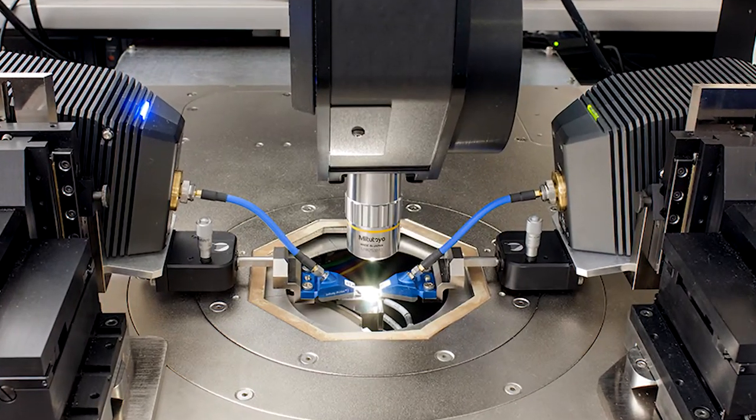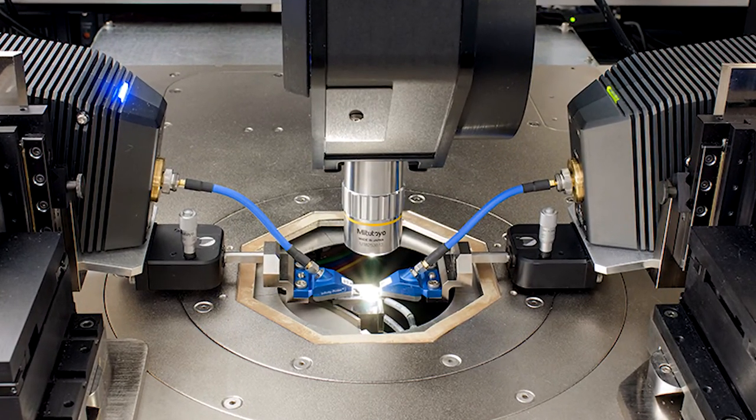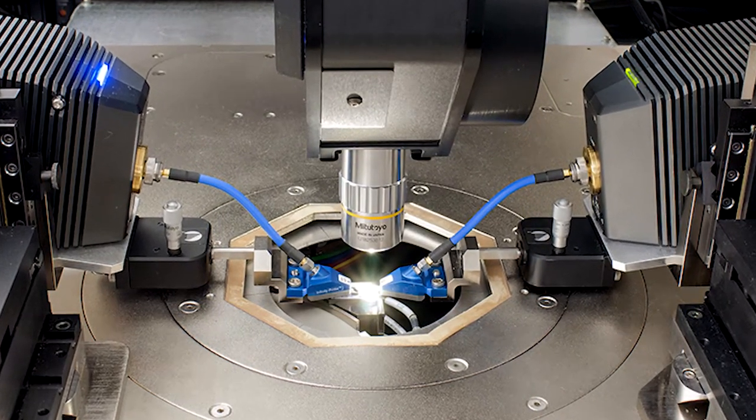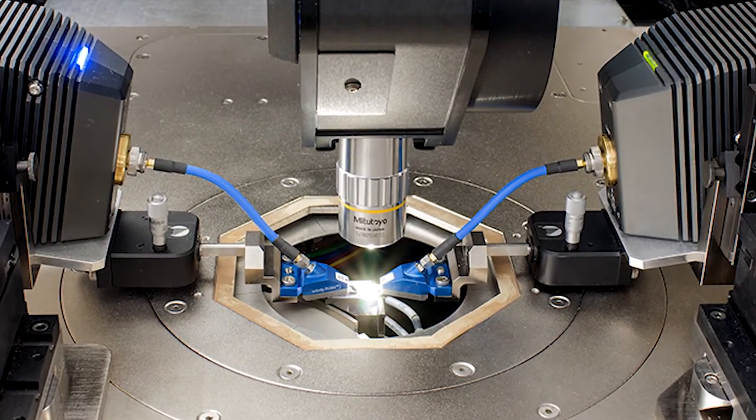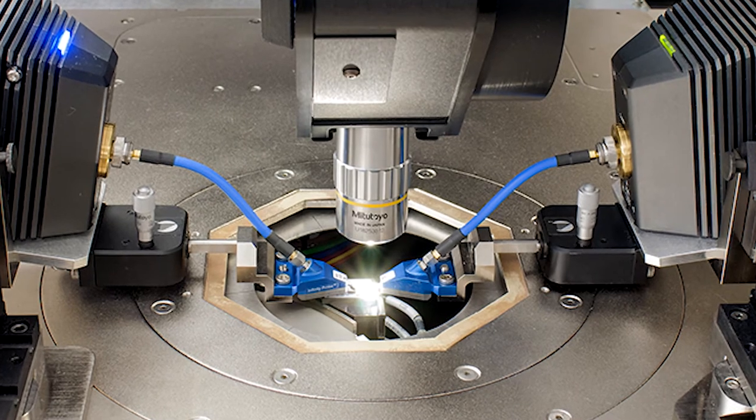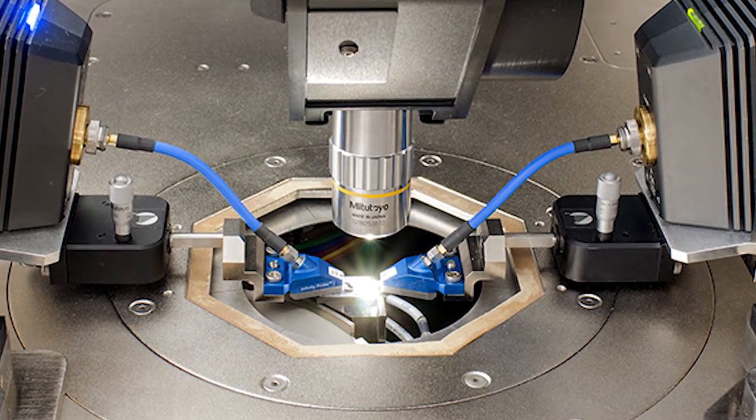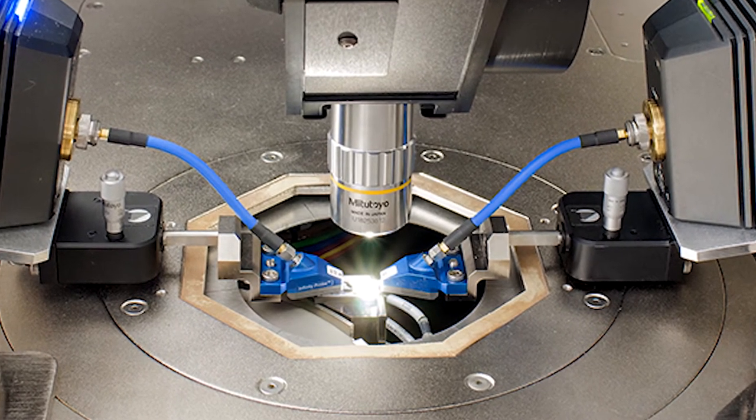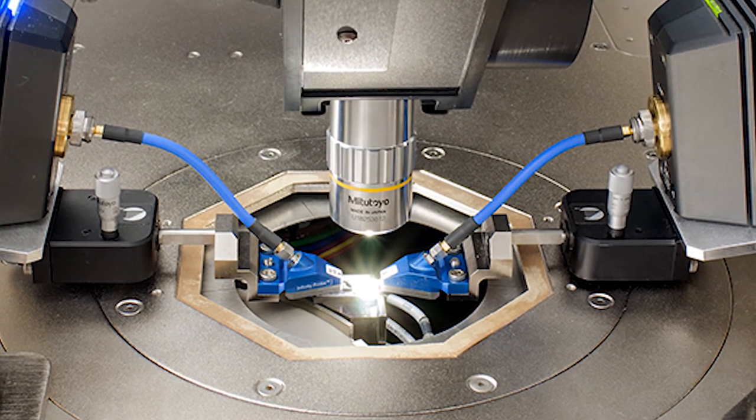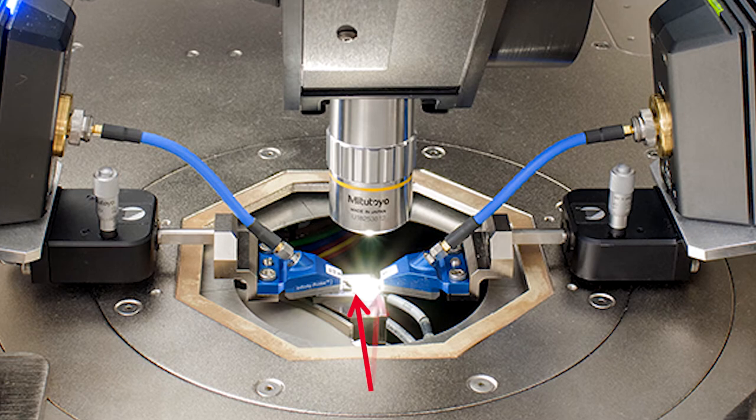Anytime you want to measure on-wafer S-parameters up to microwave frequencies, you will need to calibrate the RF fixture and probes such that S-parameter measurements will be referenced to the probe tips.